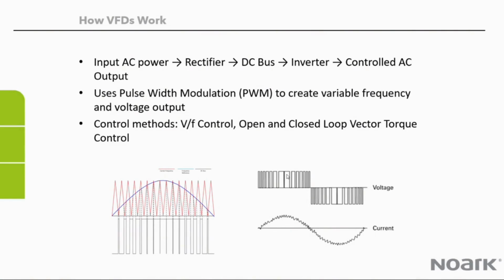One of the common things I hear is people will take a voltmeter and measure the output of the drive to see what voltage is outputting, and sometimes it'll be higher than the input voltage. You say, how can that be? This thing's making energy. Well, it's really not. Your meter is trying to interpret this square wave on and off, and it doesn't do a good job. There are a few meters out there that do a very good job. They've got some filters and such, but overall, this is what actually goes to the motor.